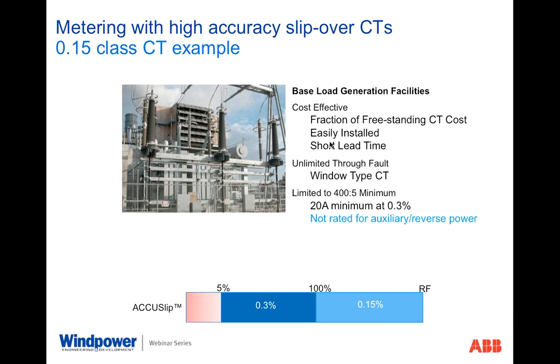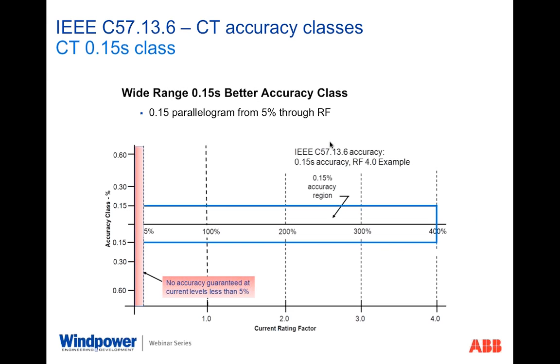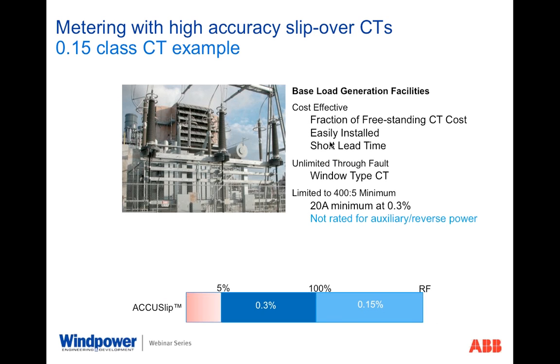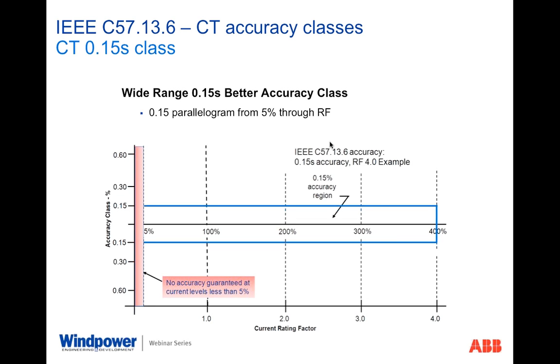Now, given that performance, we have a lot of devices out there that we can bring to bear for different applications in the 0.15 class. In this particular situation, we have class 0.15S defined for high accuracy applications specific to the wide range requirements. So this was the effort on the part of IEEE to say, okay, we're going to try to standardize on a device that meets the performance closer to the wind farm developer, the connected utility to meter this power flow up onto the transmission grid. So they came up with the 0.15S class. And the 0.15S class says that we will maintain 0.15% maximum error from rating factor value, which you see out here is rating factor 400% of the nominal ratio current, all the way down to 5%.